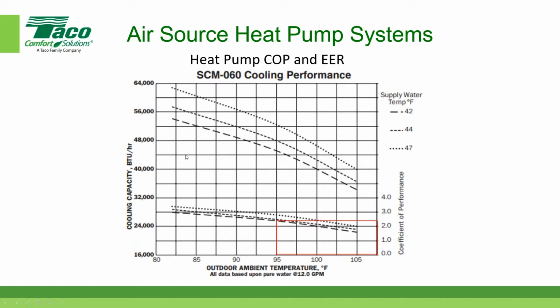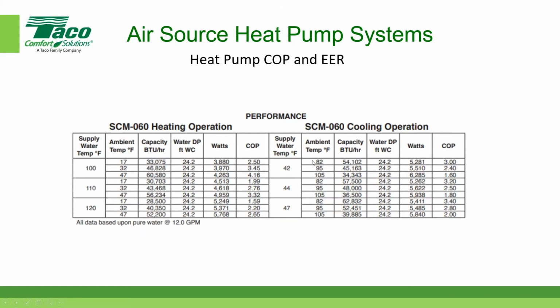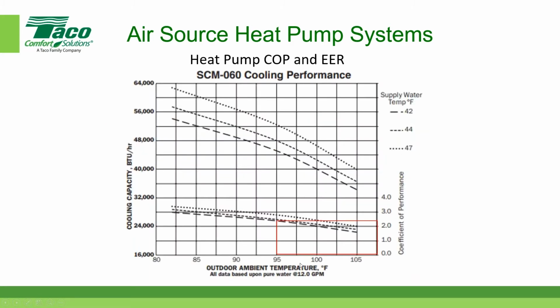You can see that this is 40,000, that's 48,000, halfway is 44,000. So you can see that that value is probably around 45,000, and that's consistent with what's on that chart over here, around 45,000. And then the COP, again at 95-degree ambient, we're producing 42-degree Fahrenheit water. You can see the COP is around 2.0.